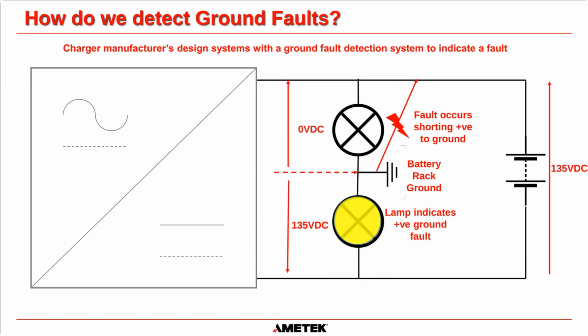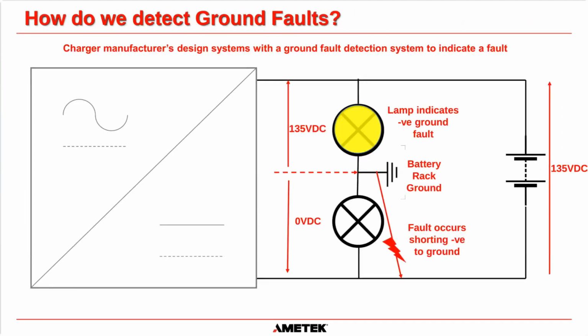A lot of people get confused when they say, well, that lamp is on the negative side, that's a negative ground fault. No, that's not how it works. The design is, if you have a positive ground fault, that one goes out, and then obviously all of the potential goes across this one here. And that is the positive ground fault light. And obviously, the reverse is true. If we have a negative ground fault, so negative is now a hard fault to ground, then this lamp will go out, and this lamp will have full potential across it, so it will be fully bright. And that indicates that we have a negative ground fault. So that is the most basic form of ground fault detection.